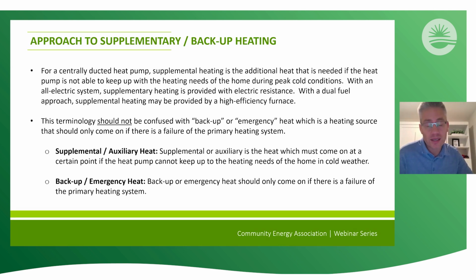One thing we do find in the industry, directly with contractors, is there's a lot of confusion between the terms backup or emergency heat versus supplemental heat. We'd like to draw the distinction so that folks aren't using those interchangeably. Supplemental and auxiliary is the heat that has to come on when the heat pump can't keep up to meet the heating needs of the home in colder weather. Backup emergency heat is the heat that should only come on if there's a failure of the primary heating system. We like to keep the distinction so that folks understand the differences, especially in rural, remote communities, as Rob hinted at earlier, where you'll typically have backup heating systems because you don't have access to contractors to solve issues when equipment is down or needs to be serviced.